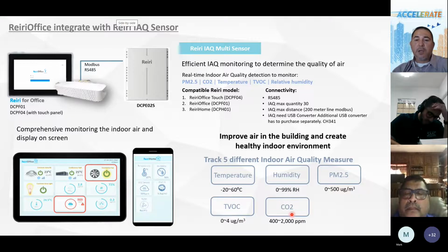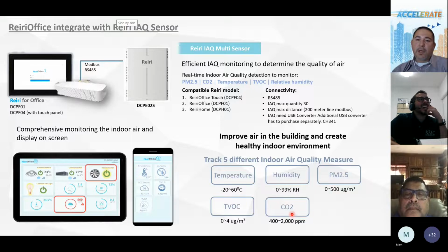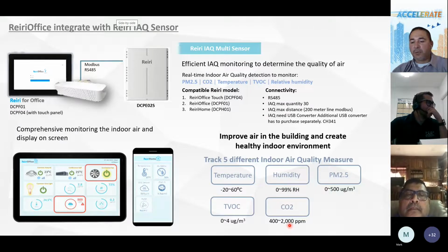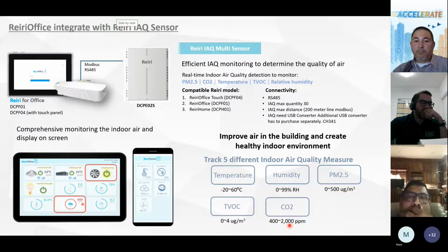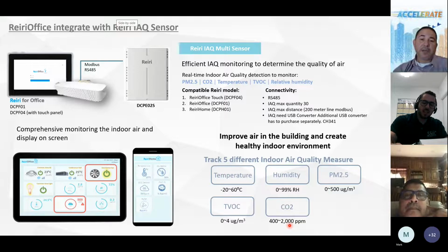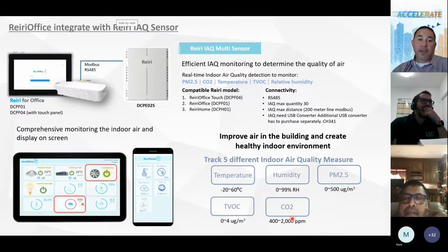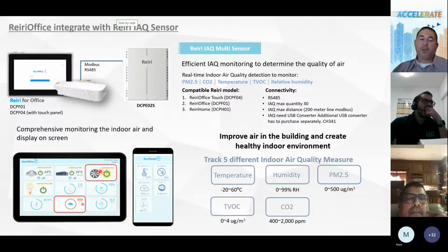And the CO2 - the way we can do it is, let's say for example we're in a school, we make a range on the controller to measure the PPMs up to 2000, because after 2000 the students can fall asleep. If you reach that level, I can trigger the fan to turn on and change the air inside the space, so I can improve the quality of air inside the space.